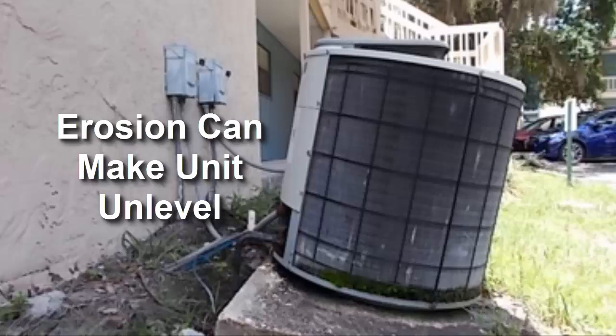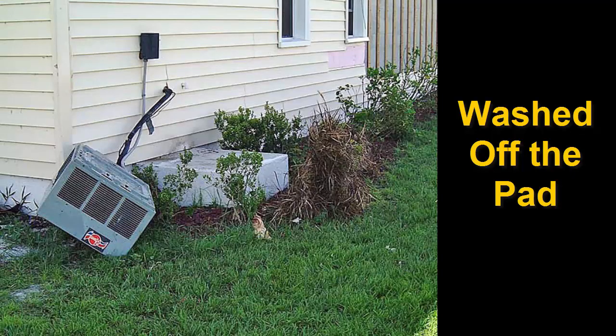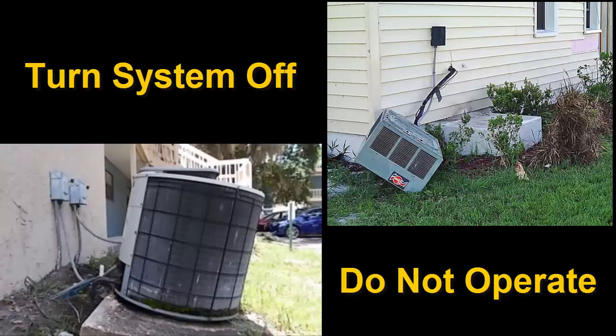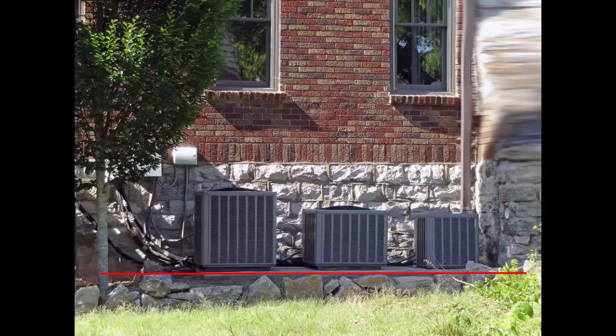Erosion, gullies, and mudslides can cause the pad the outdoor unit is sitting on to shift as the heavy rain washes away the earth beneath and beside it. The result is that the unit is no longer level, or in extreme cases, the unit has washed partly or completely off the pad. If you encounter either of these situations, turn the unit off and do not operate it until the unit is made level again on a firm footing.